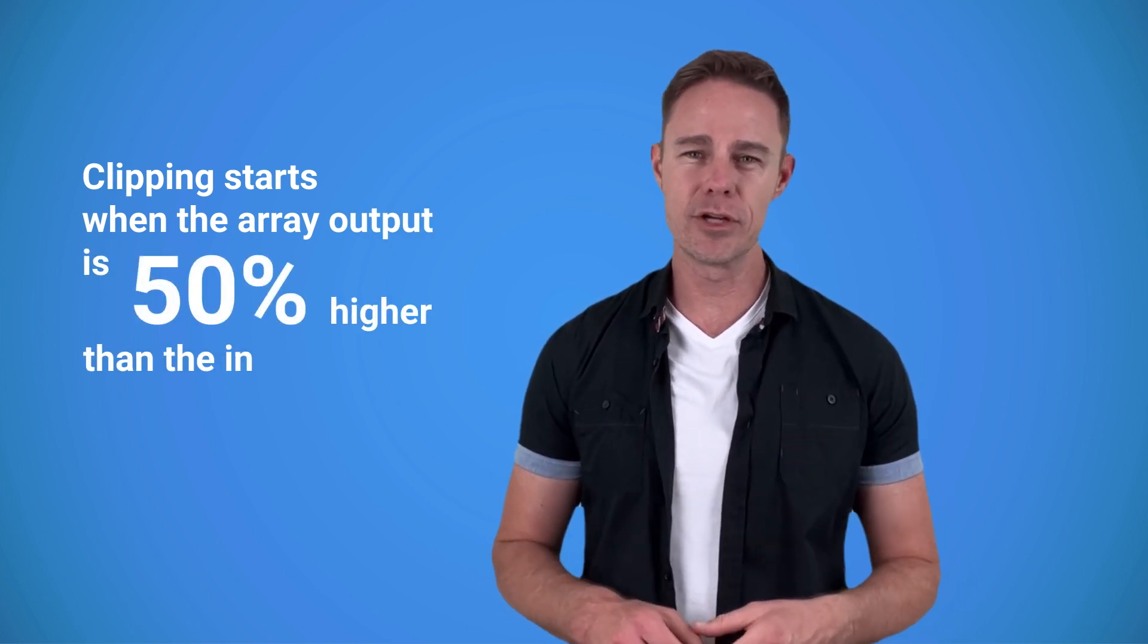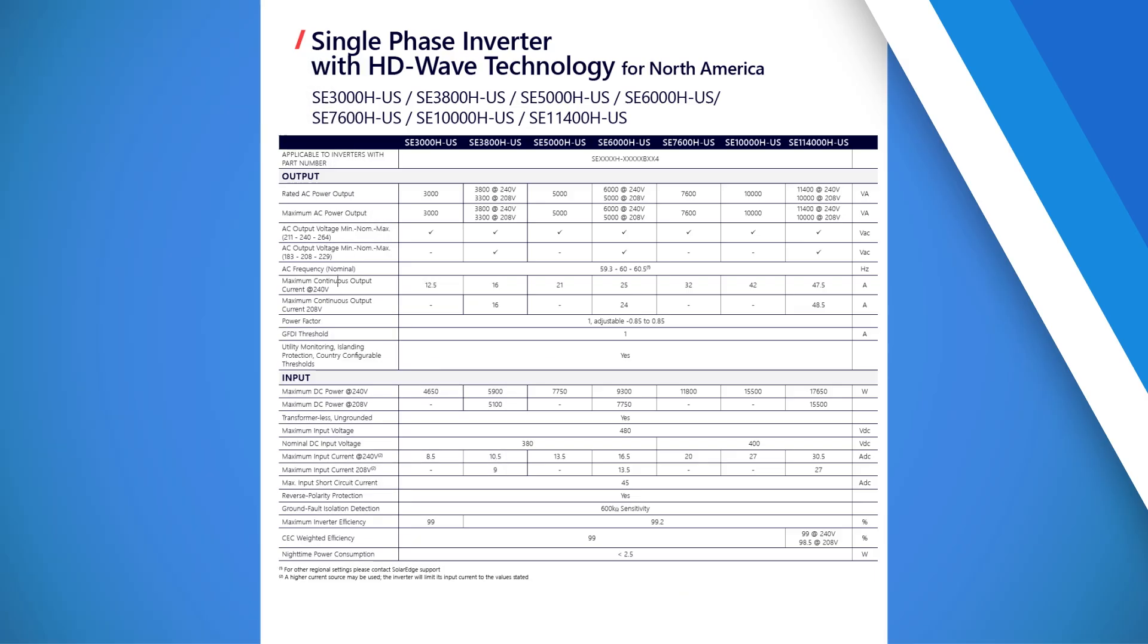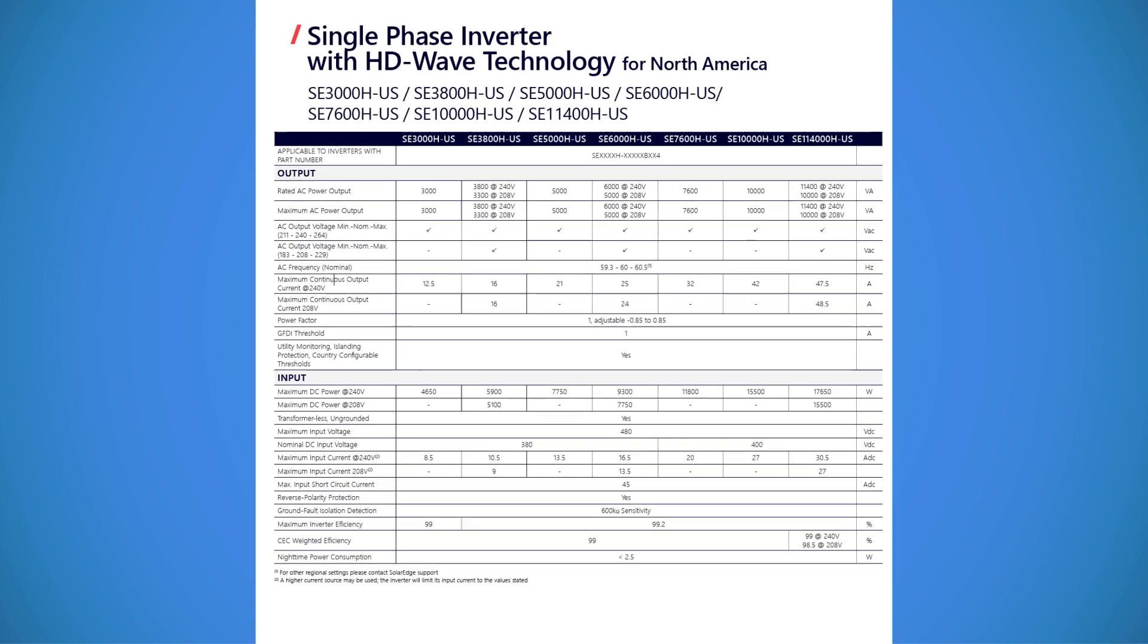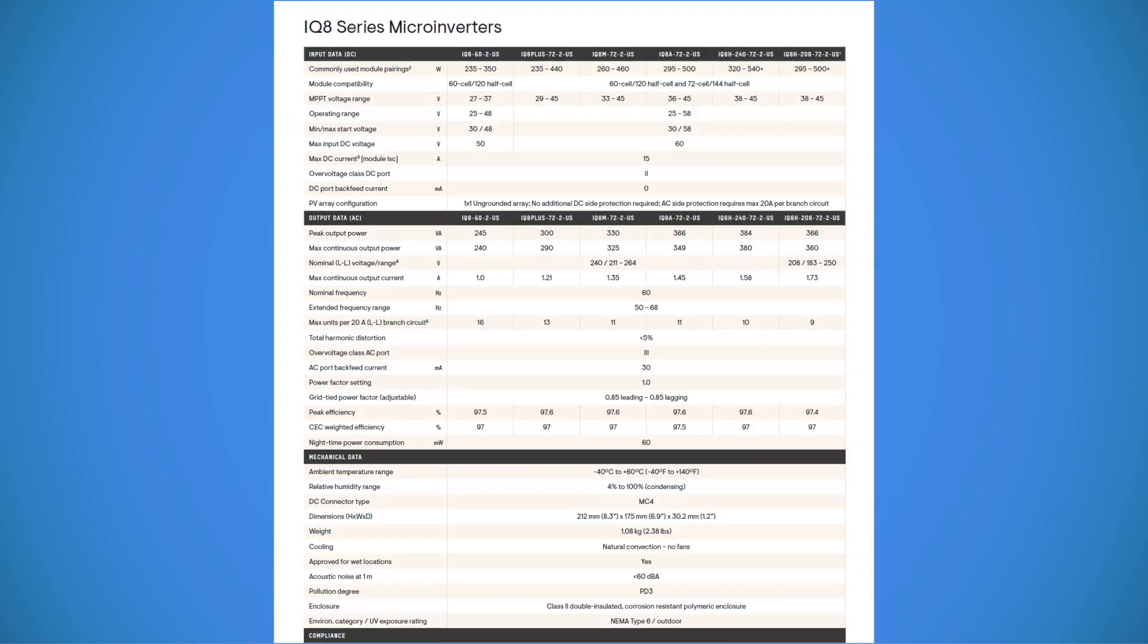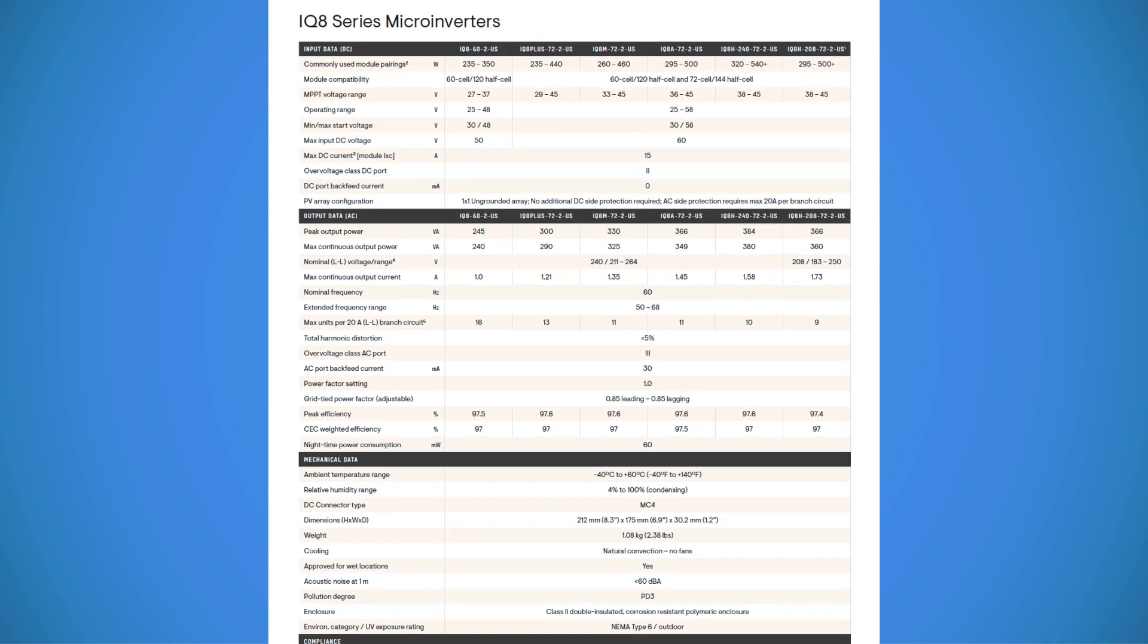Every model is different, but on average clipping starts when the array output is 50 percent higher than the inverter's capacity. You also don't want to install a solar inverter that's too big for your system because the inverter is going to be most efficient if it's running close to its overall capacity. Another thing you should check is that the voltage and current from your panels should not exceed safe levels for the inverter. You can find the maximum voltage and current input in every inverter's data sheet.